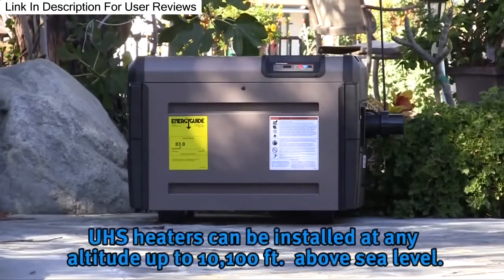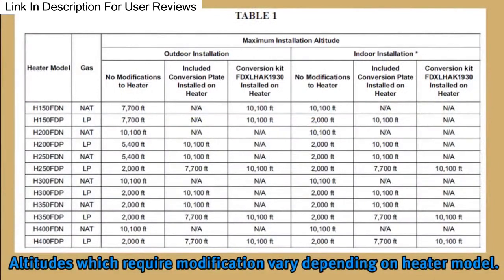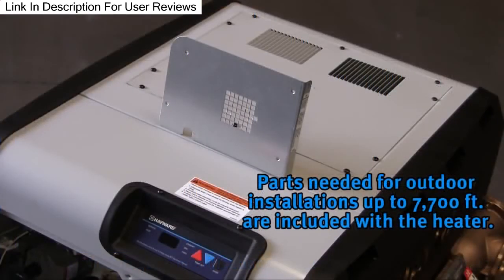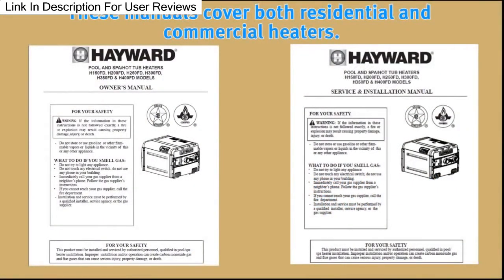The heater may be installed at any altitude up to 10,100 feet above sea level, provided the appropriate modifications are performed. The altitudes which require modification vary depending upon the model. Parts necessary to convert the heater for outdoor installation at altitudes up to 7,700 feet are included with the heater. Consult the installation manual for more information on high altitude installations.